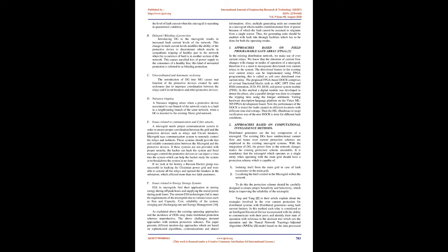C. Uncoordinated and automatic reclosing. The introduction of DG into MG causes malfunction of the protective devices created by auto reclosures due to improper coordination between the relays and circuit breakers and other protective devices. D. Nuisance tripping. A nuisance tripping arises when a protective device associated with one branch of the network reacts to a fault in a neighboring branch of the same network, when a DG is inserted into the existing microgrid network.